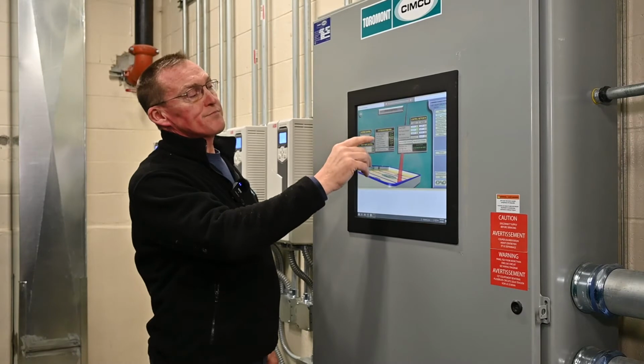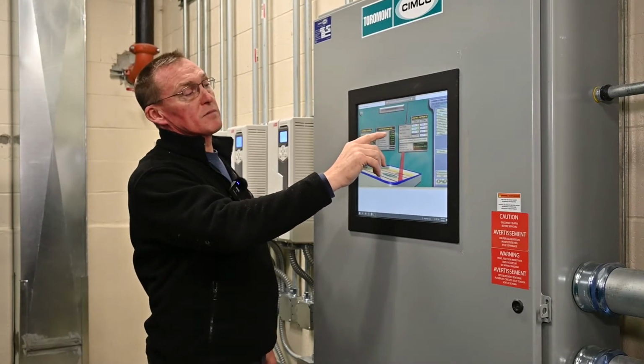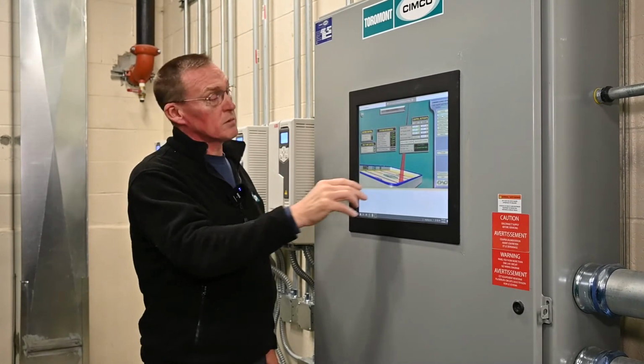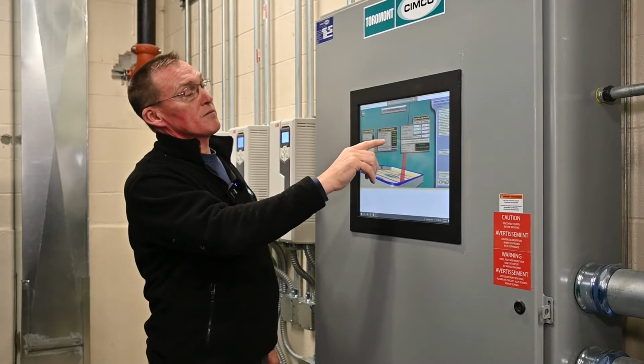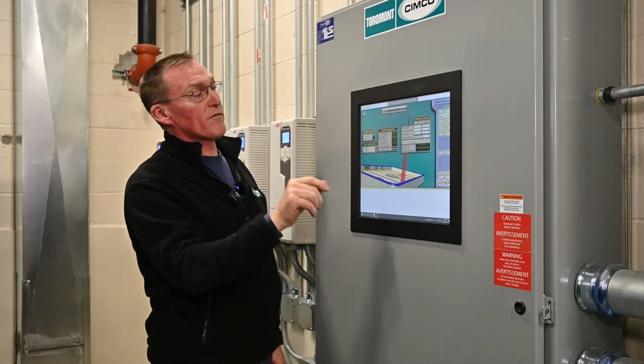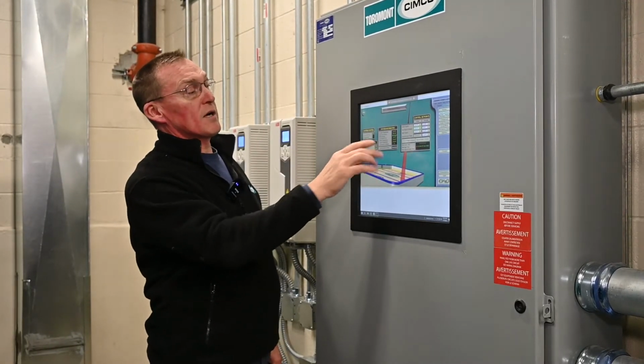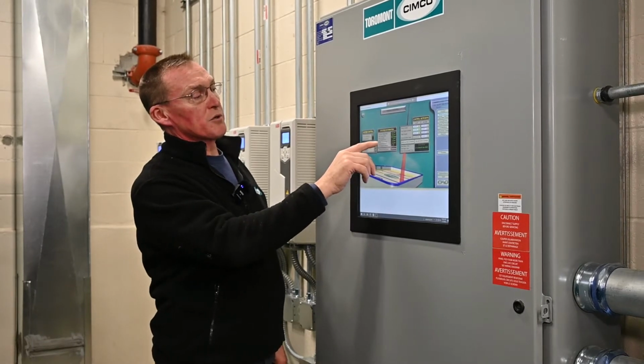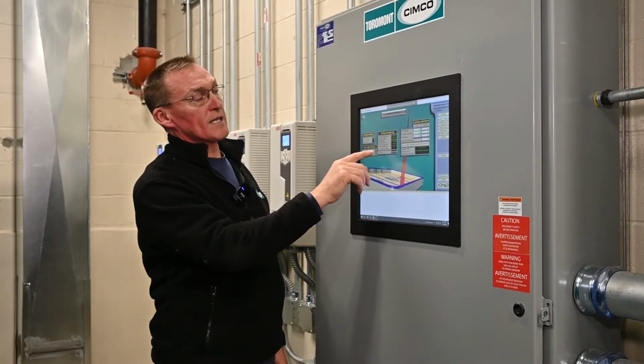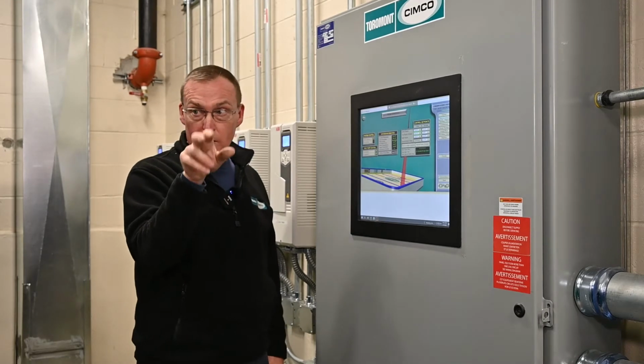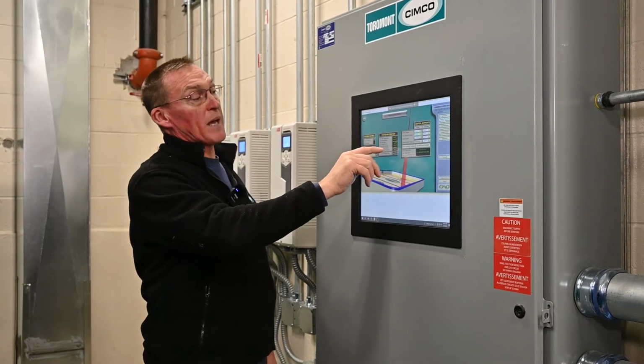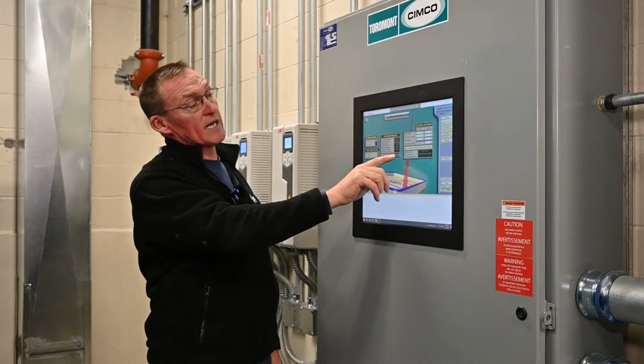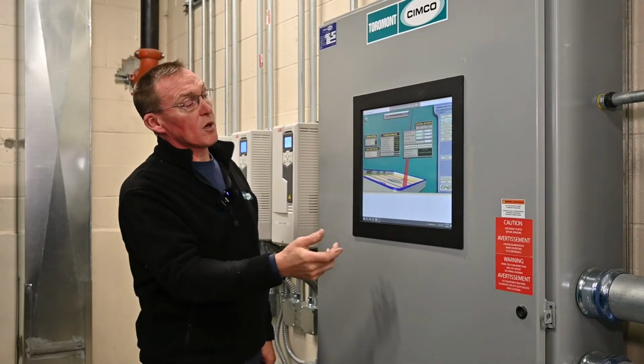System information. Ice slab temperature, you have a sensor in the floor. Rink temperature, rink humidity, the sensor's mounted on the far wall. Ice error, I'll go over that outside. And then you have return temperature, supply temperature. That's the glycol literally in the mains going out to the floor. And then compressor demand, whether or not the system is satisfied, or whether it's calling.